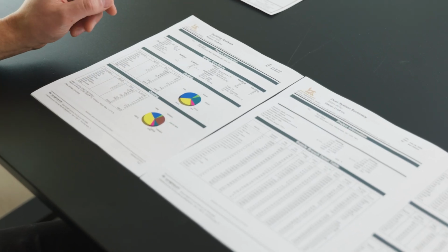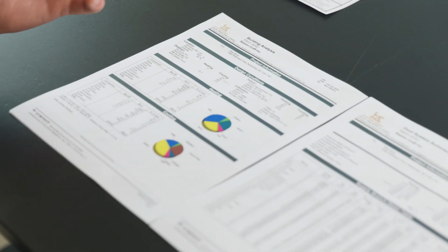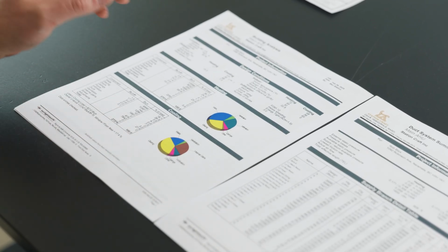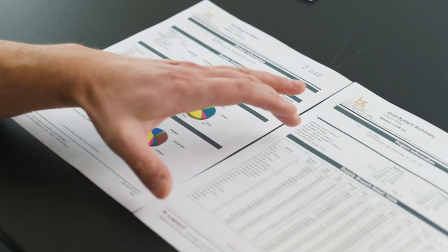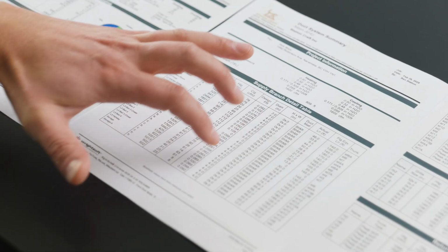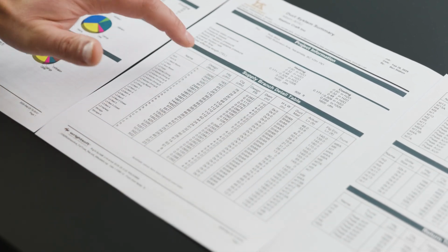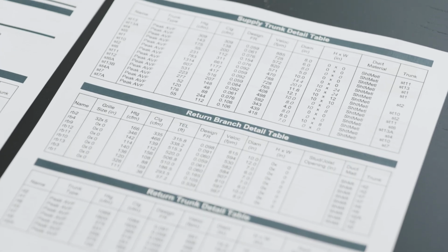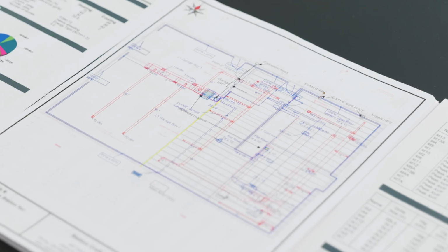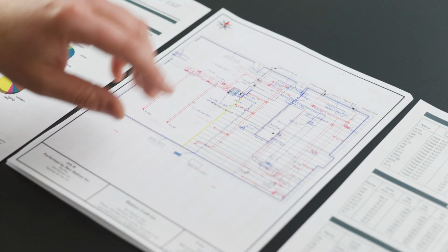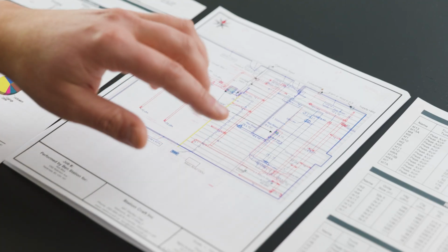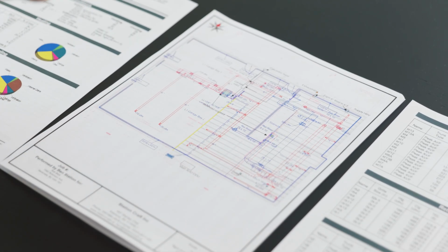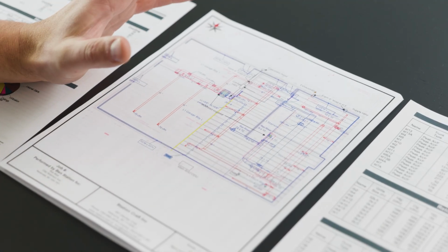So once we've taken care of our inputs and we know what our loads are going to be and how we need to design our duct system in order to service that, these are the things that we'll get out of this. On here, we have a supply branch table that tells us what size of ducts we're going to be servicing for which room in order to meet which of the design conditions, whether the heating or cooling load is the dominant. From there, we'll plan our duct runs and make sure that they're going to work with the structure of the building. We have to ensure that where we locate our supply and return ductwork, as well as the vertical stacks that go through the different floors of the house, that is going to work architecturally for the design of the building.